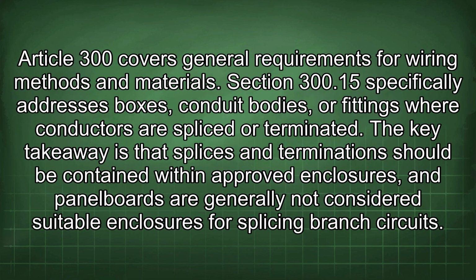Article 300 covers general requirements for wiring methods and materials. Section 300.15 specifically addresses boxes, conduit bodies, or fittings where conductors are spliced or terminated. The key takeaway is that splices and terminations should be contained within approved enclosures, and panel boards are generally not considered suitable enclosures for splicing branch circuits.